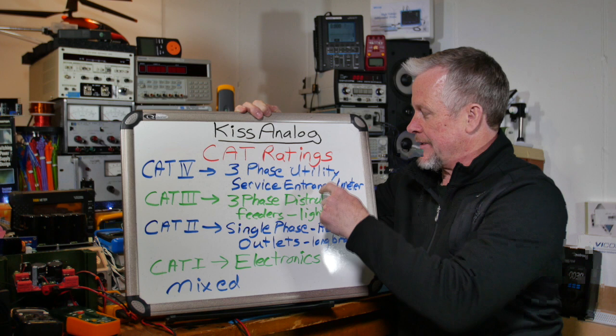So then you forget to move your leads and go to measure a voltage. Well, you have the voltage divided by 10 milliohms, and that could be like 10,000 amps. So lots of current. That's why you have those high rupture capacity fuses, because out here, that's probably all that's going to stop the current. Now, Cat 2: I'm over here on the other side of the wall, and I've got a breaker panel. I've got a 15 amp, maybe 20 or even a 30 amp breaker, but most likely a 15 amp breaker. So now you have a breaker to do a lot of the protection for you.